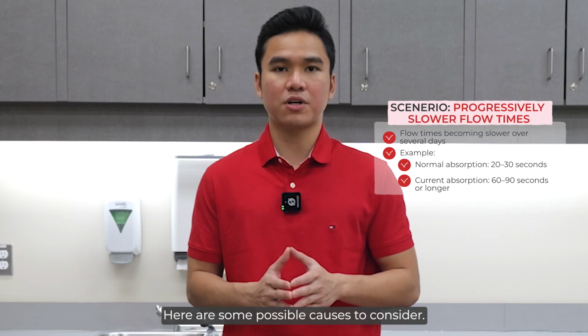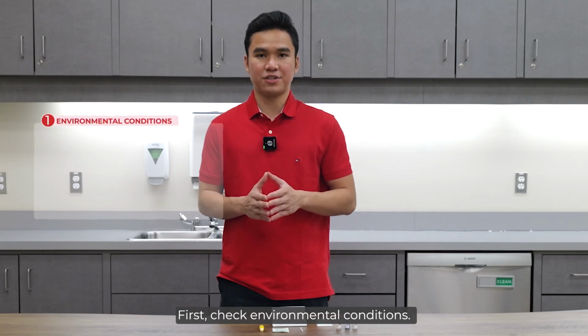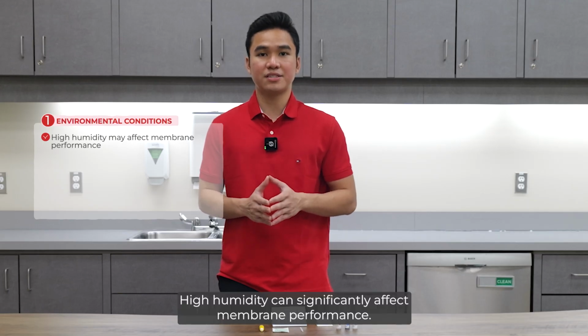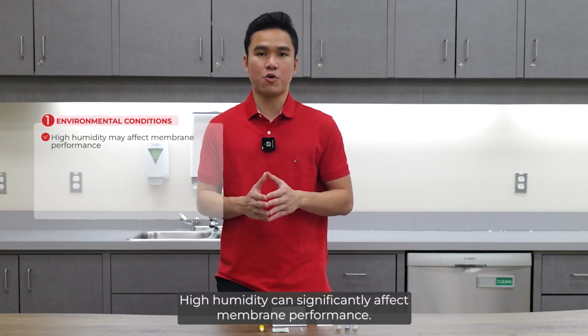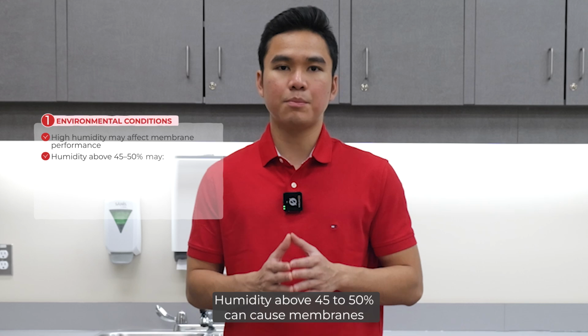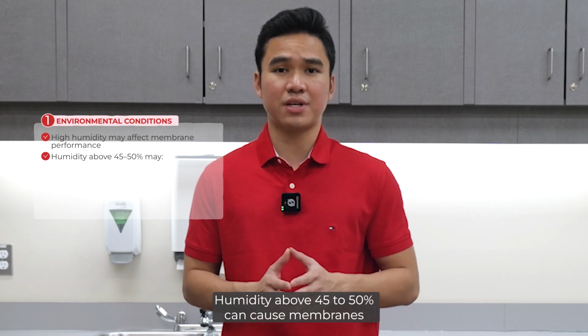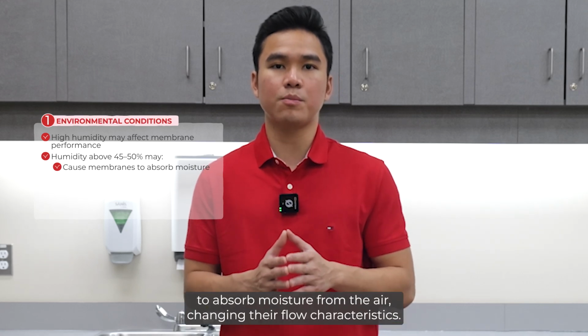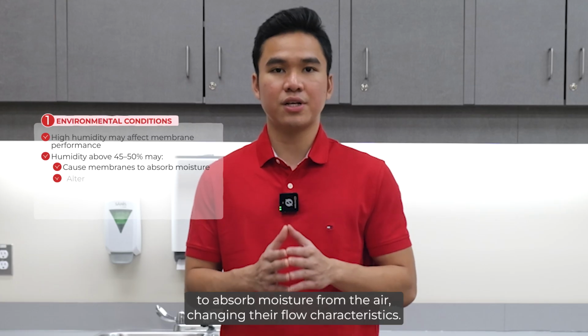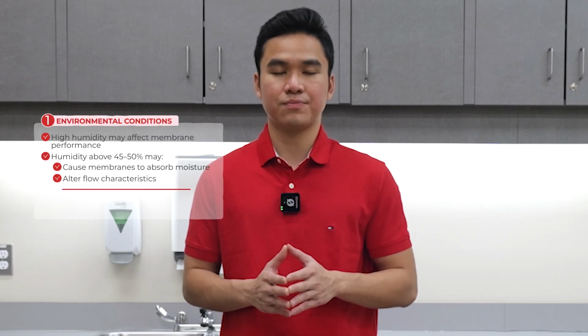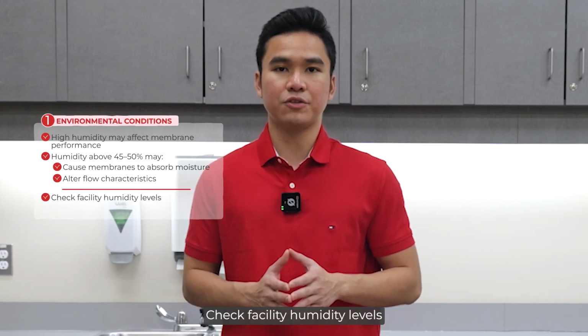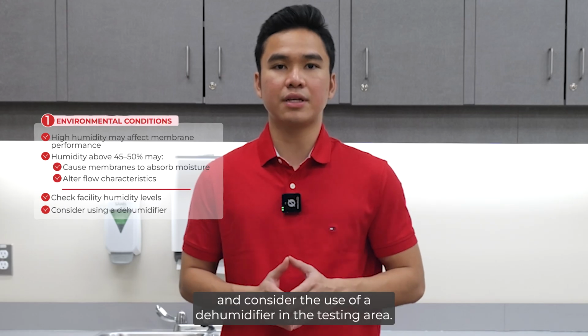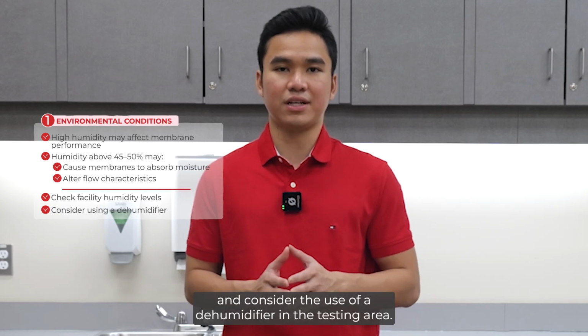Here are some possible causes to consider. First, check environmental conditions. High humidity can significantly affect membrane performance. Humidity above 45 to 50% can cause membranes to absorb moisture from the air, changing their flow characteristics. Check facility humidity levels and consider the use of a dehumidifier in the testing area.